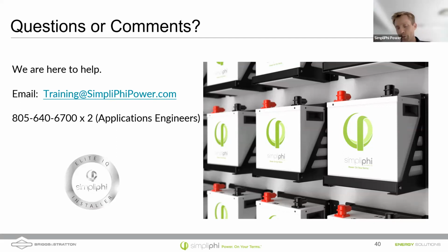If you look at the levelized cost of energy, that's the amount of cycles and energy you store and use over the lifetime of a lithium battery. You get 100% depth of discharge out of a lithium battery, while a lead acid battery is typically limited to about 50% depth of discharge, and that declines quickly with time, so you're really only getting about 30% of the energy out of a lead acid. If you look at the cost of changing that battery after 5 to 10 years, and the levelized cost including installation and other factors over the lifetime of the battery, lithium is about half the cost. There are some applications where lead may still make sense, but most companies and homeowners are realizing you get more bang for your buck with lithium.